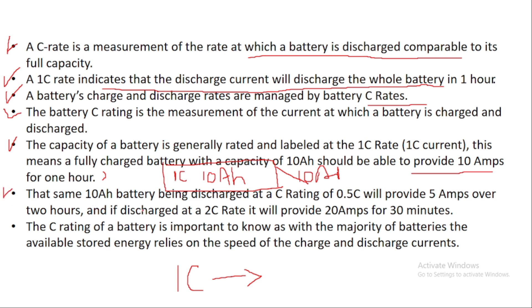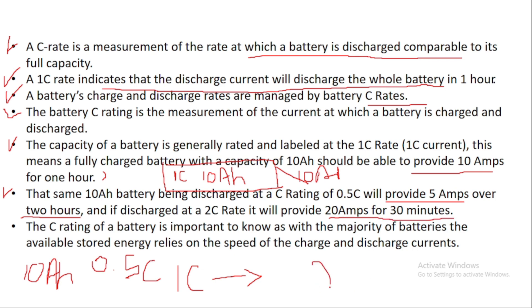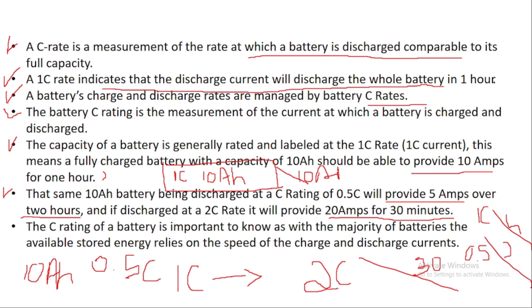That same 10Ah battery being discharged at a C-rate of 0.5 — suppose your rated capacity is 10Ah and C-rate is 0.5 — then your battery pack will provide 5A of current for two hours. And if it is discharged at 2C rate, it will provide 20A for 30 minutes. If your battery C-rate is 1C, it will take 1 hour to discharge completely, and if your battery pack C-rate is 0.5, then it will take 2 hours to discharge completely.